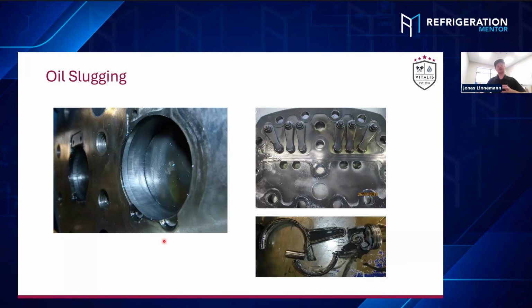But if you get small amounts of liquid back over time, you can see from the direction where the oil is traveling through the lubrication channels inside the compressors how the bearings wear off differently from that liquid because of the lack of lubrication. If you get too much oil back, you can see that the piston area, the compression area, is sometimes full of oil. You can see that on the valve plates. And as soon as you send a broken compressor back to the manufacturer, they will tell you what happened. They do their reports, their analysis, and you can tell pretty precisely most of the time why a compressor failed. And then you need to go back and see what the cause in the system was.